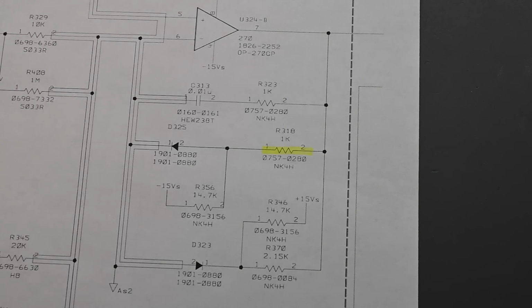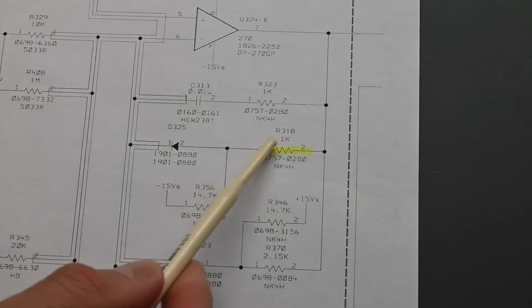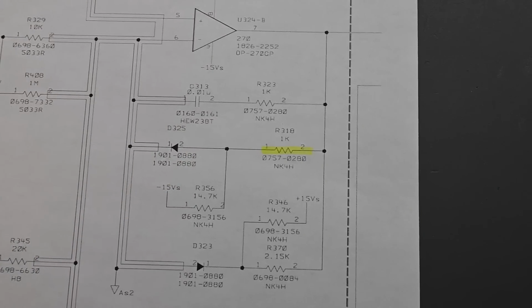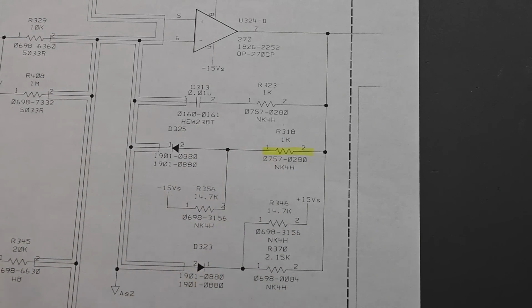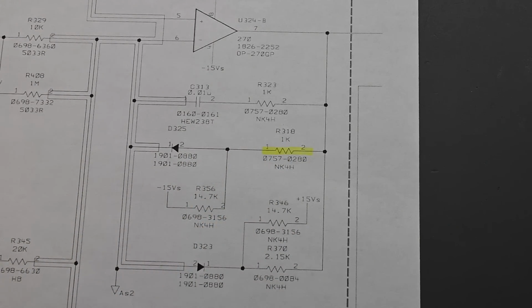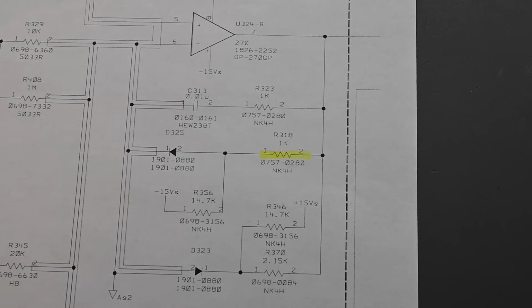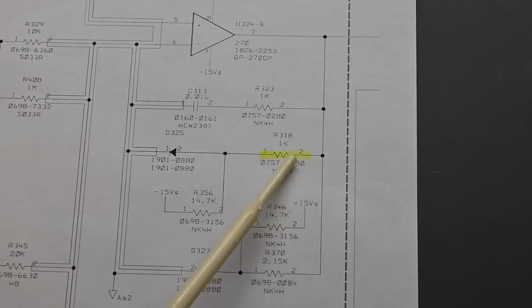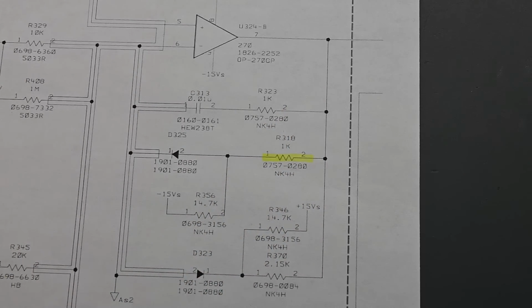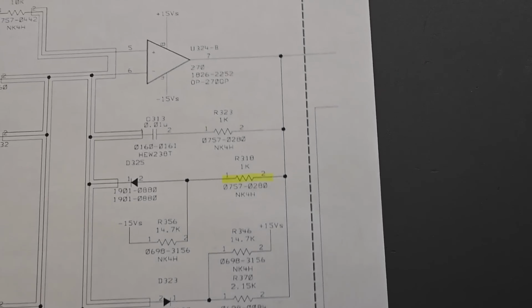Earlier in the testing, I did notice that the power supply went into a constant current mode unexpectedly. I think you probably noticed that I said something was unexpected when it was operating, and I'm wondering if this had something to do with that, because this does say current control. I'm wondering if this circuit really isn't functioning correctly with this resistor missing. So again, it'd be interesting to return this and see how the power supply functions, and if it is wildly out of spec and doesn't work correctly, I can always remove it. But again, that power supply image that I saw on the photo online of the circuit board, this resistor was installed. All right, so I hope that kind of clarifies where we're at on the troubleshooting, and it's a rather odd situation with these missing components.